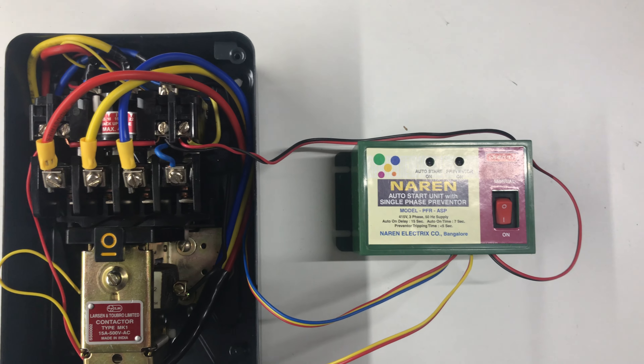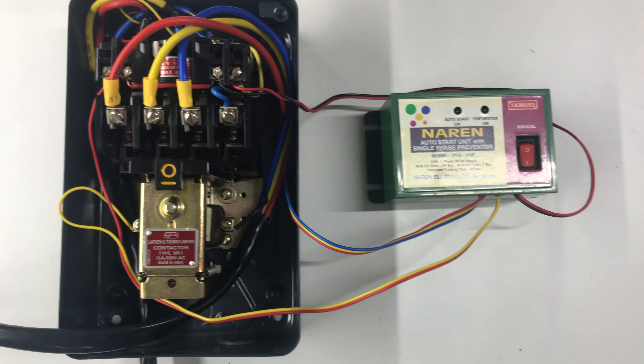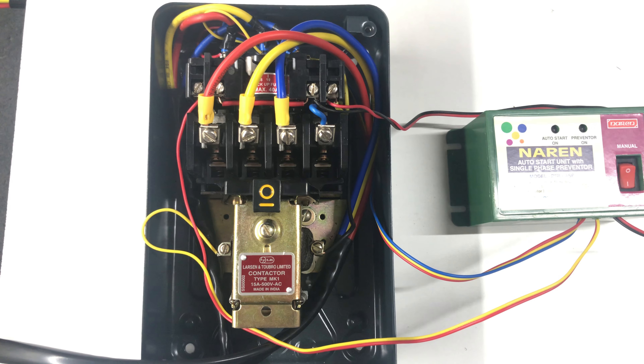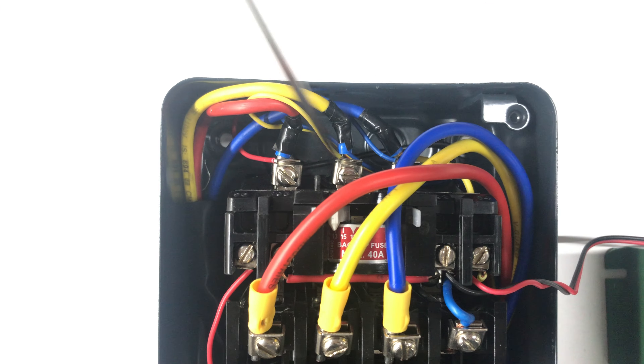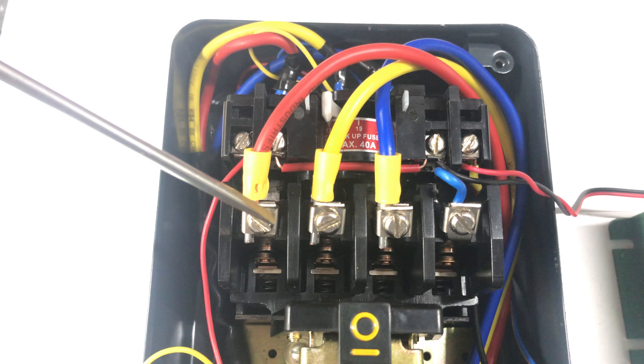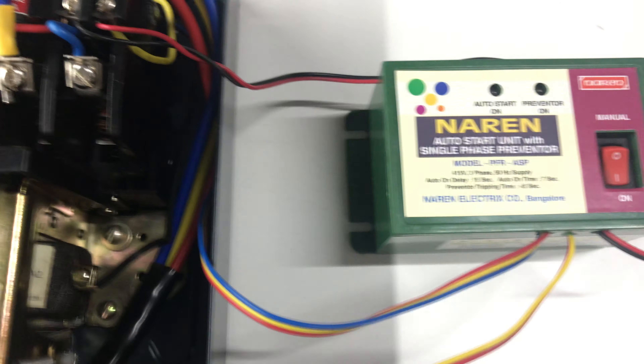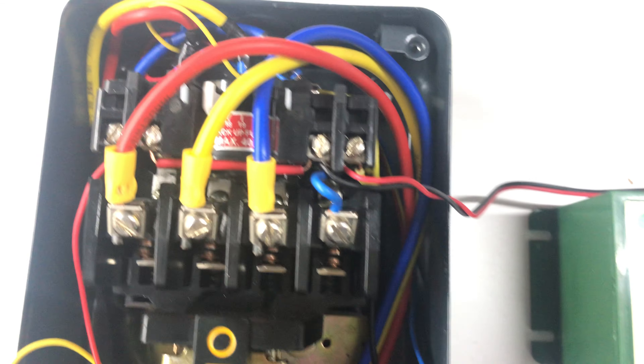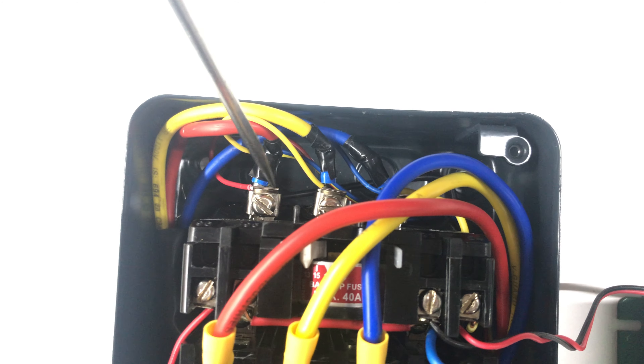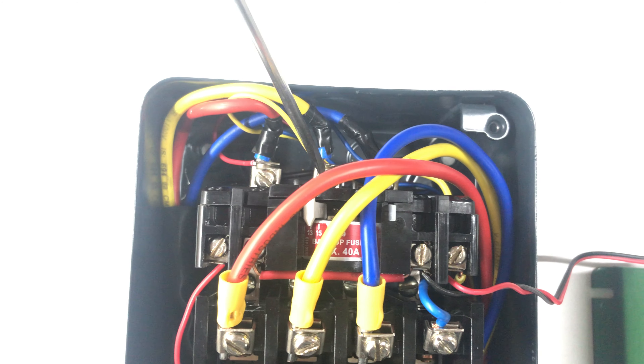We will quickly have a look at how to make these connections. The starter connections should already be there. The incoming three-phase supply is going to these three points — the load carrying wires — and the motor cables are connected to the motor ends. The Naren PFR-ASP's first three RYB cables have to be connected to the same point where the supply gets in, so we have taken the red, yellow, blue connections to the same three points R, Y, and B.